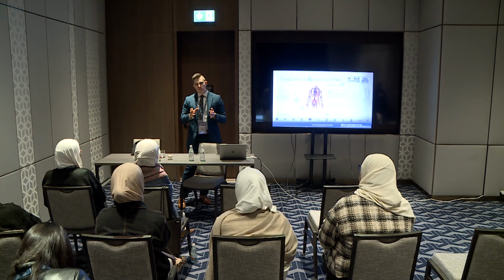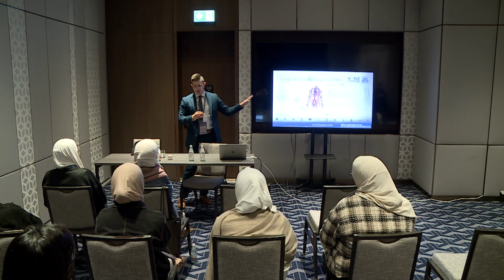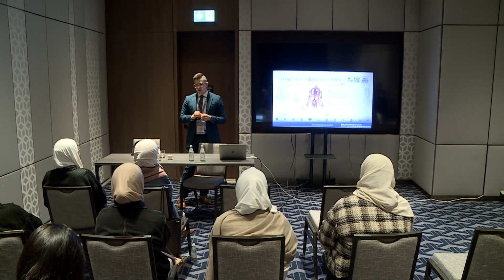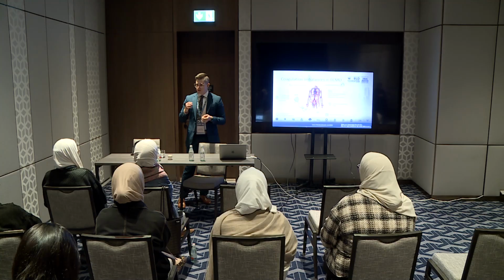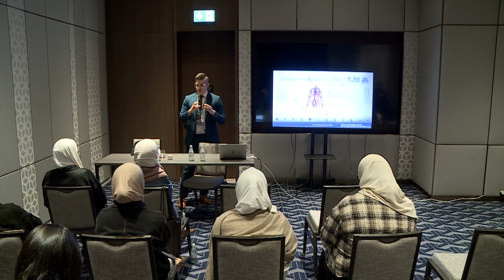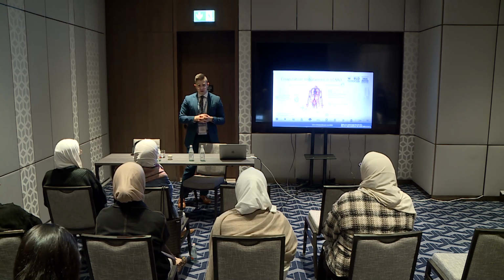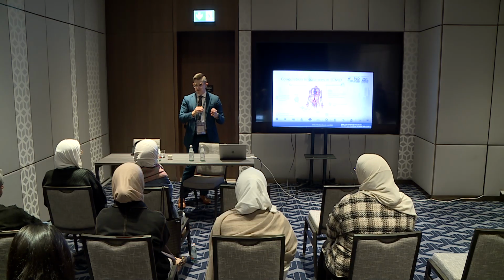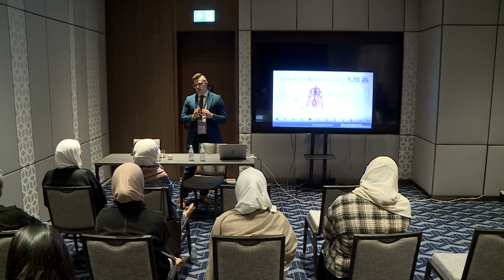Hemodialysis usually has a blood flow rate around 200 to 300 milliliters per minute. ECMO is around 4 to 5 liters per minute, and so the tubing is very large. You also require a mechanical pump, whereas hemodialysis usually uses a roller pump because it's a much smaller blood flow rate. And also the hemodialysis just passes through filters. There are no artificial membranes outside of the filters, and so it's much less risky from that standpoint.